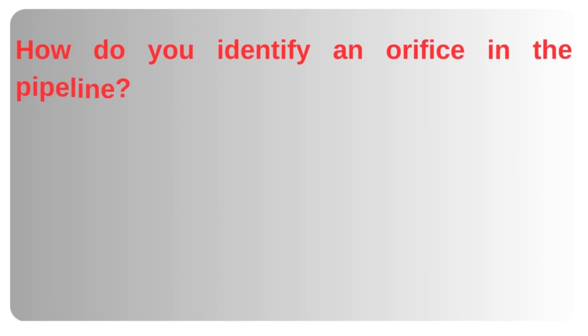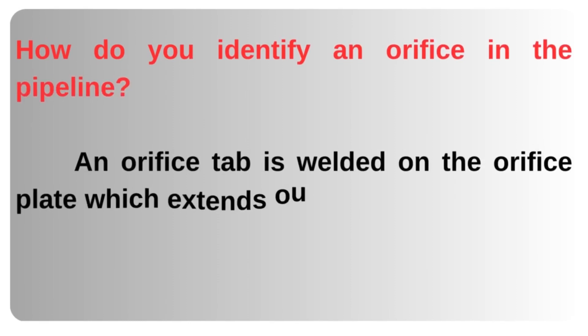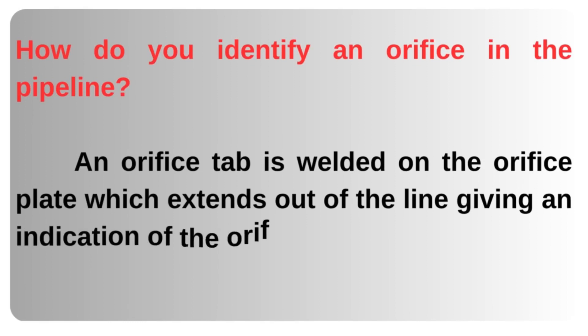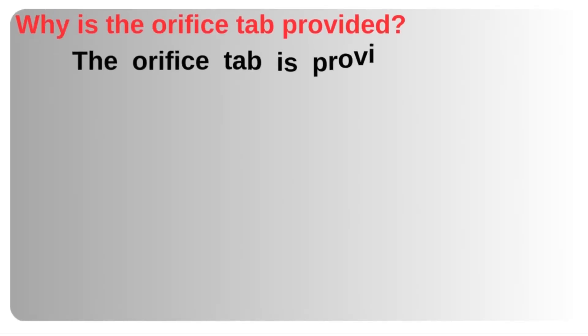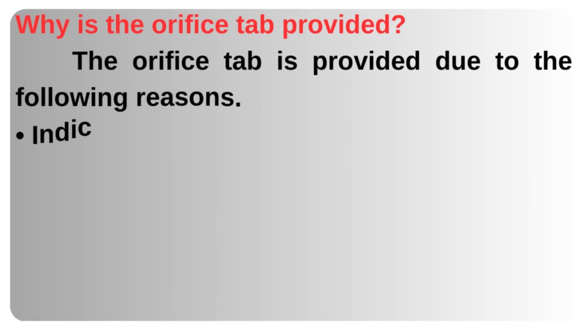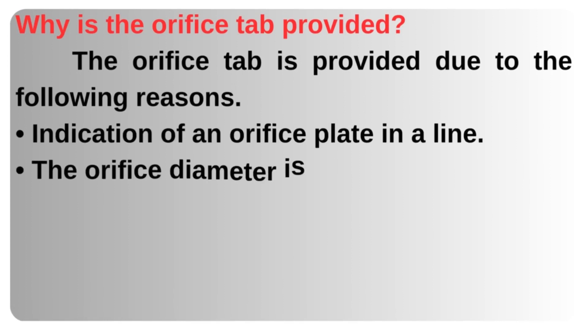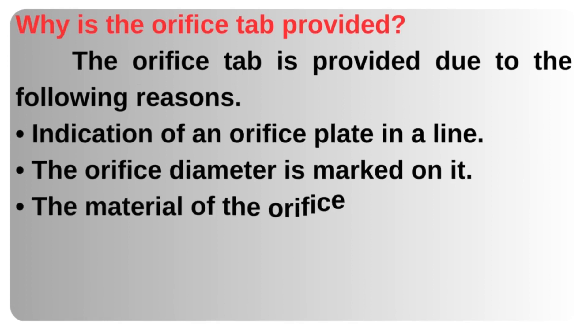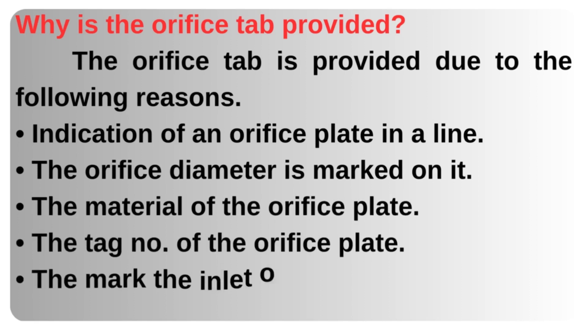How do you identify an orifice in the pipeline? An orifice tab is welded on the orifice plate, which extends out of the line giving an indication of the orifice plate. The orifice tab is provided for the following reasons: indication of the orifice plate in a line, the orifice diameter is marked on it, the material of the orifice plate, and the tag number of the orifice plate.